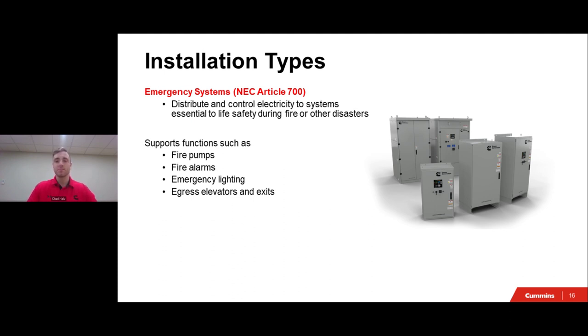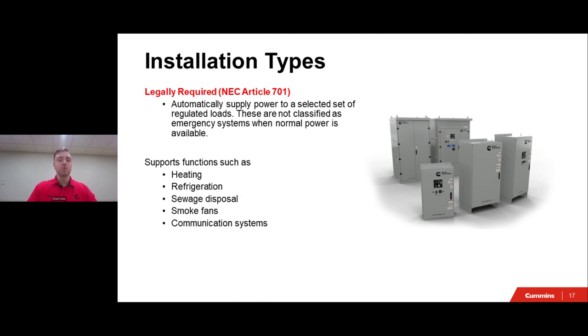Next up is a legally required system. So what is a legally required system? This is a system that automatically supplies power to a selected set of regulated loads, not classified as emergency systems, when the normal power is unavailable.